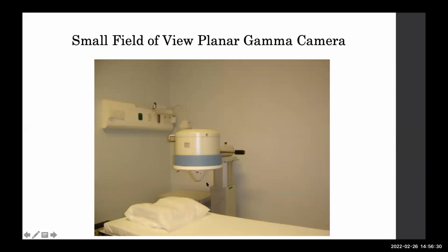This is a special gamma camera, a small field of view camera with pinhole collimators, used for imaging small organs like the thyroid. Like when we image with ultrasound and see a nodule, we can then see whether it is a cold nodule or a hot nodule. This pinhole collimator is used with small field of view gamma cameras. They are less often used, but a few departments still have very small field of view planar gamma cameras.